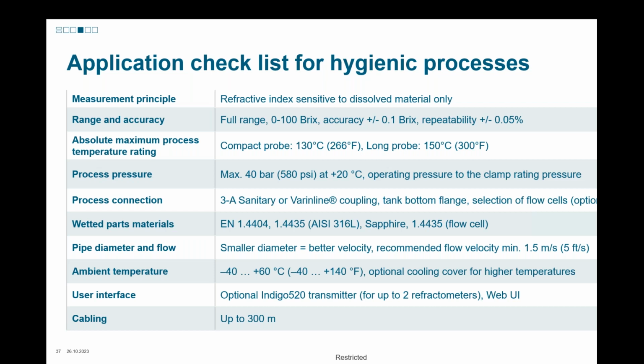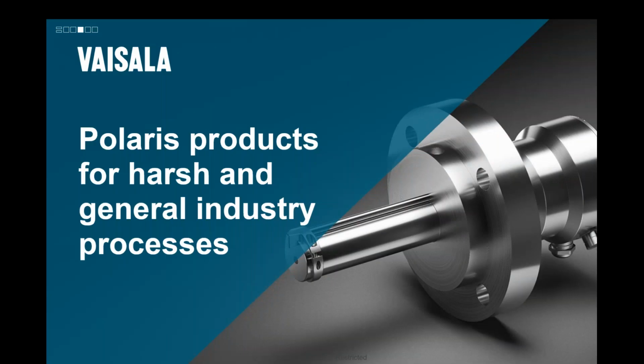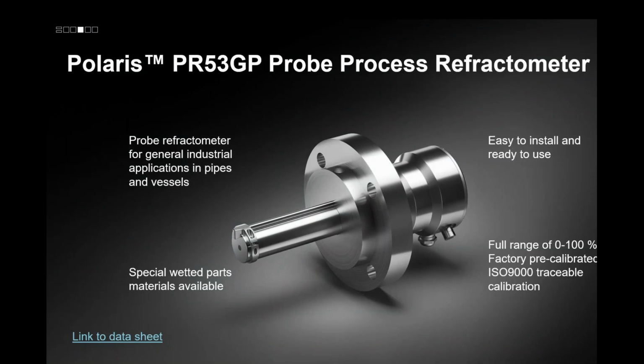Pressures up to 580 psi or 40 bar. Yeah, so I don't want to read the chart here, but you can read it yourself. So this is our flanged version. This is our GP. Again, very similar to the other sensors, except it's an ANSI class flange. And you can see this one here has our cleaning system. It may not be real easy to see, but you'll see parallel to the snout of the sensor, there's a tube. That tube runs from the flange, and you connect process steam or process water.